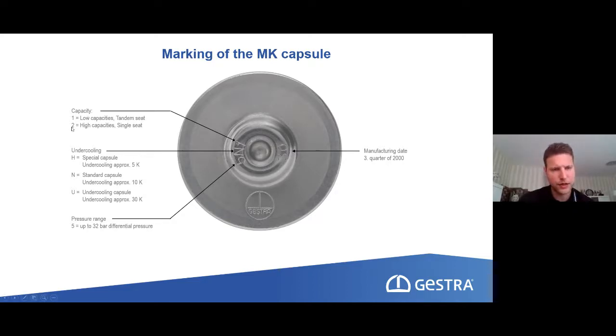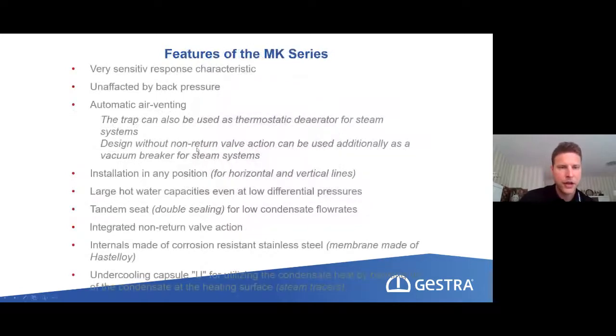So if we have the 2 stamped in here, we will have the single-seated version. Here on the other side, we will have the manufacturing date. If we need to know it, it might also be a good idea to know how long this might be in operation. So the MK series is very good when it comes to air venting. The air venting part of it is very good, and this is why we also attached it to the UNA, the ball float steam trap, because it reacts in the fastest way. It's very sensitive because it is rather close to the saturated curve, and you can also install it in horizontal and vertical situations.